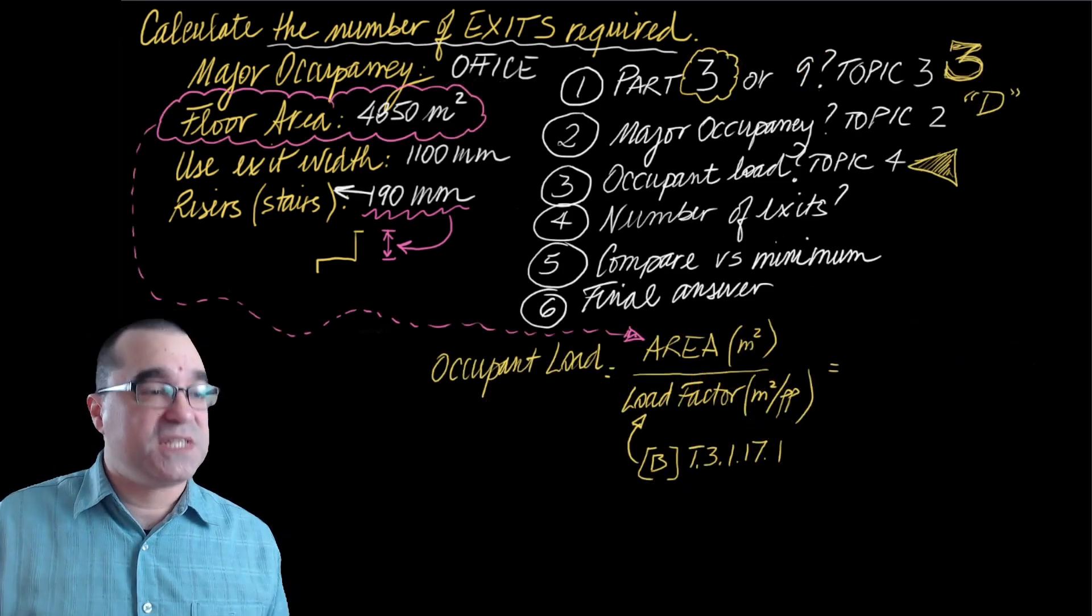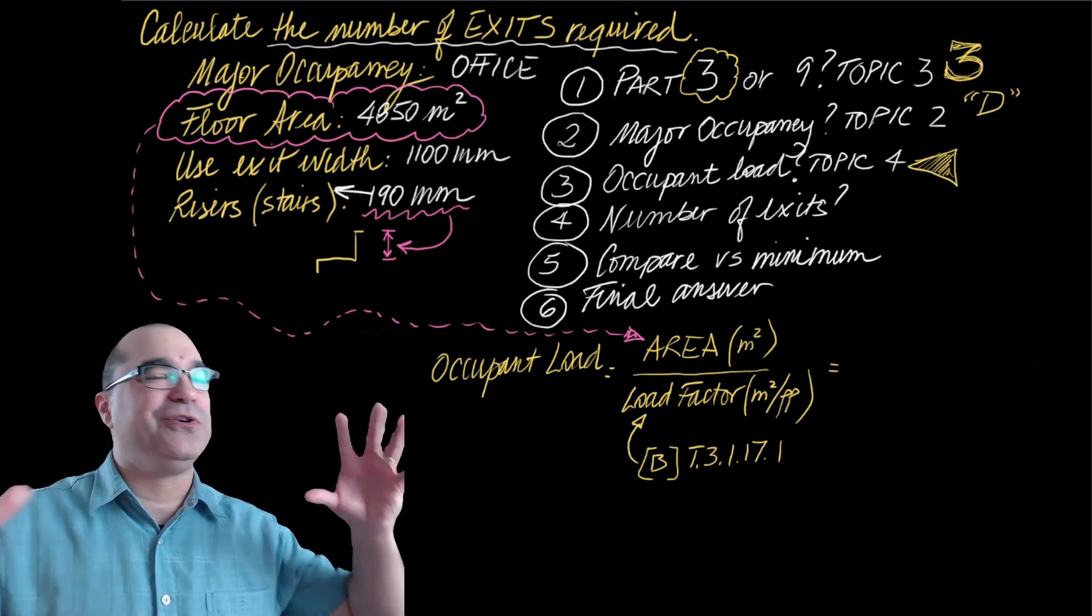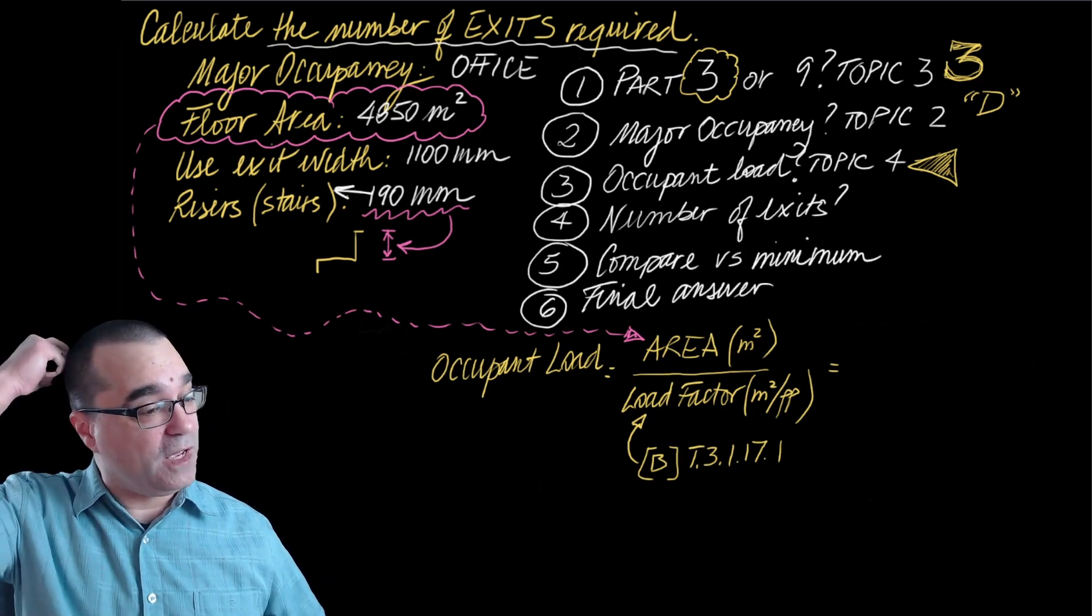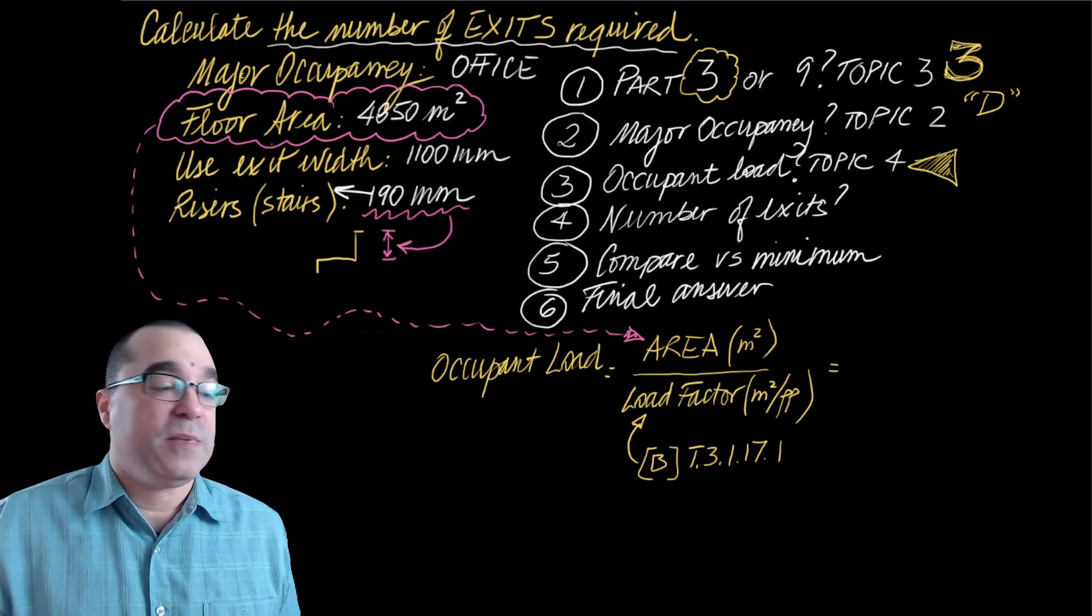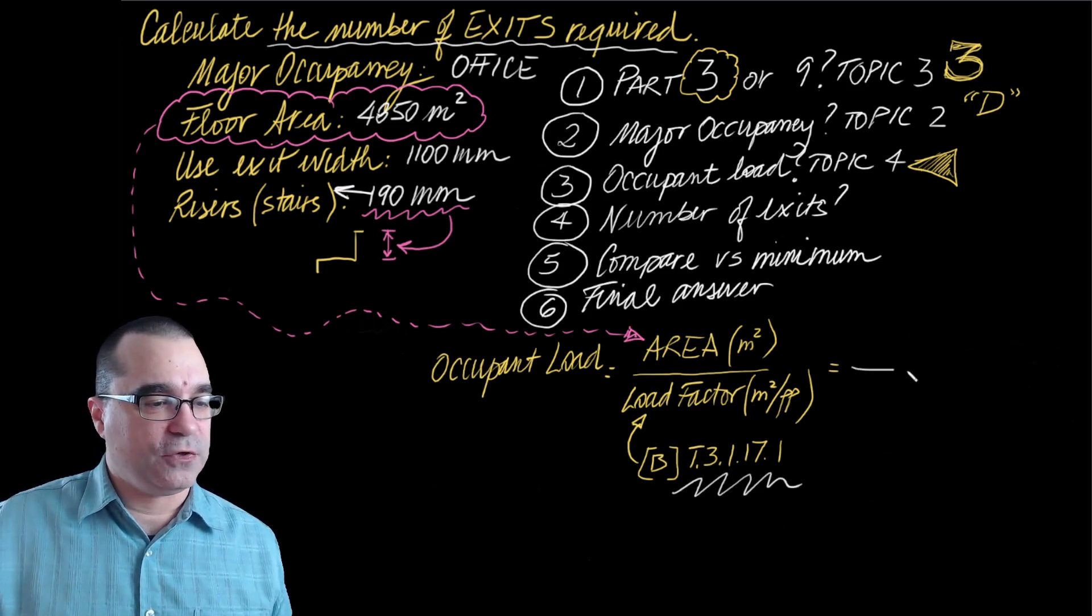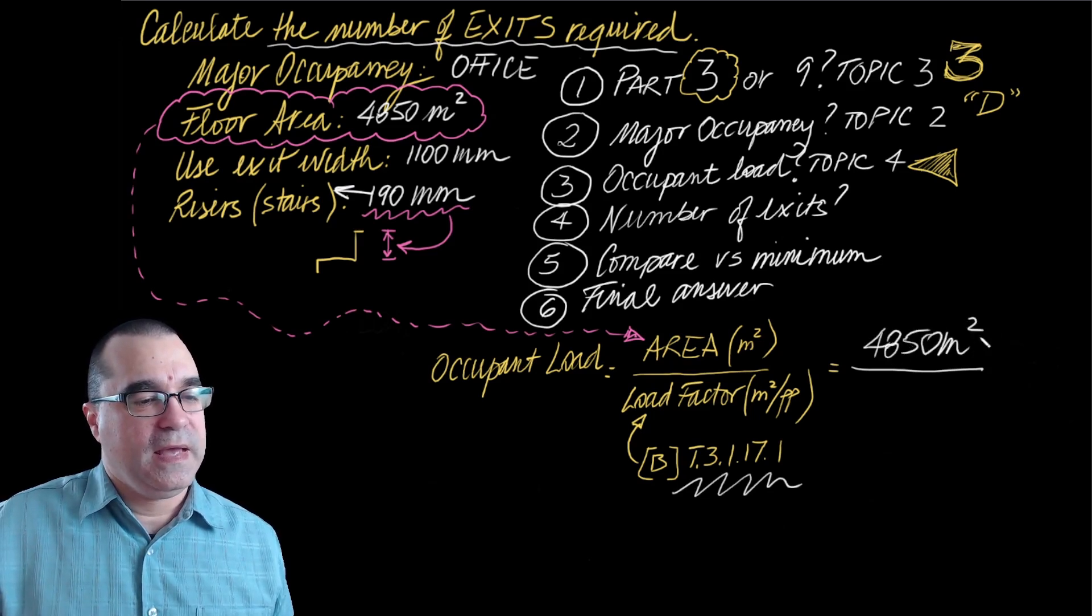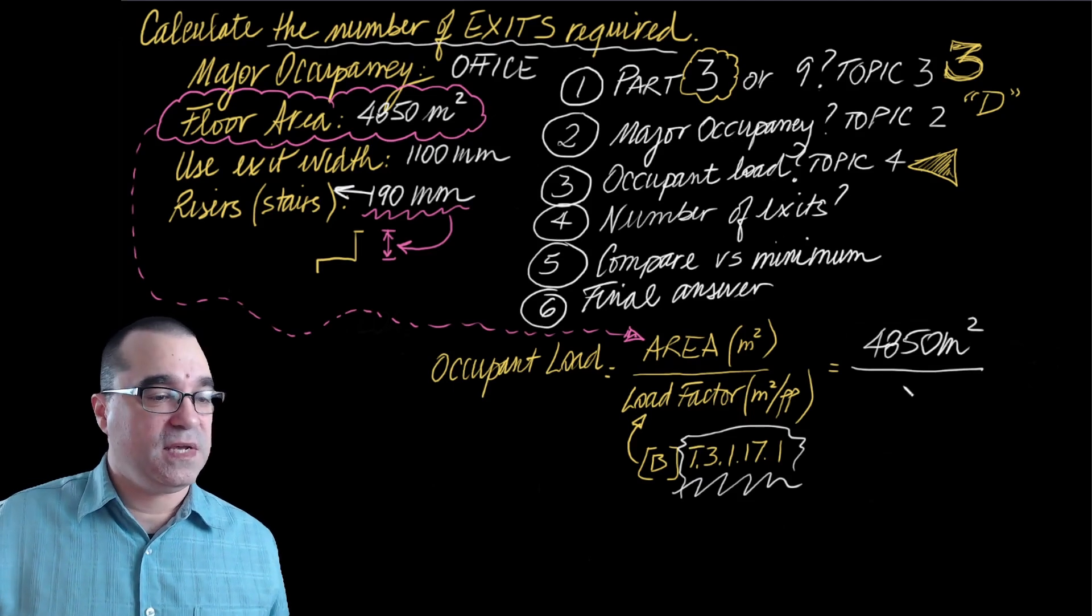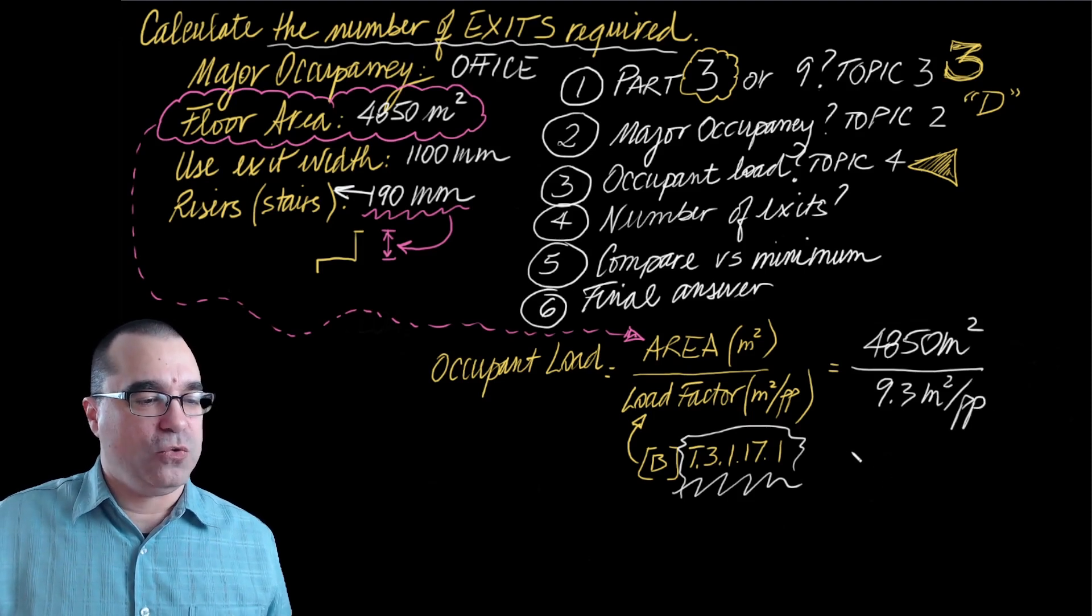Let's move on to step number three. Under step number three, we have to use what we learned in topic four to figure out the occupant load. Occupant load is fancy building code speak for how many people are using that space. So it's based on the floor area, and it's the ratio between the floor area and the occupant load factor that's obtained from table 3.1.17.1. So I'm going to figure that out. The area is 4,850 meters squared. And from table 3.1.17.1, for a D major occupancy, office space, the occupant load factor is 9.3 meters squared per person.